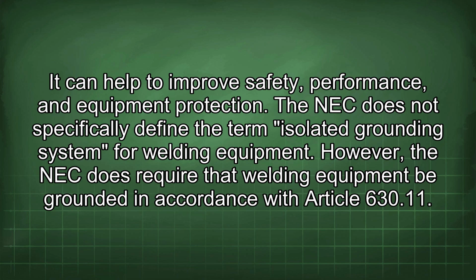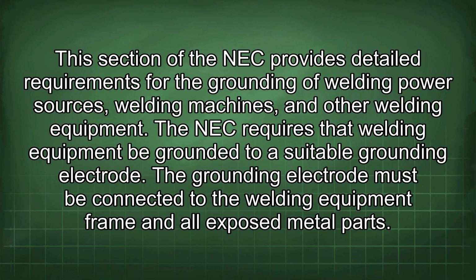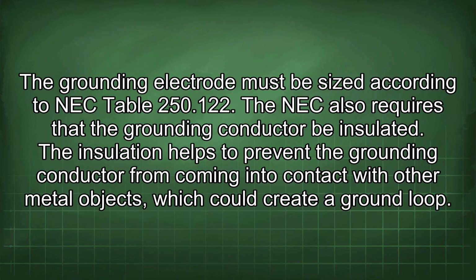The NEC does not specifically define the term isolated grounding system for welding equipment. However, the NEC does require that welding equipment be grounded in accordance with Article 630.11. This section of the NEC provides detailed requirements for the grounding of welding power sources, welding machines, and other welding equipment. The NEC requires that welding equipment be grounded to a suitable grounding electrode. The grounding electrode must be connected to the welding equipment frame and all exposed metal parts.